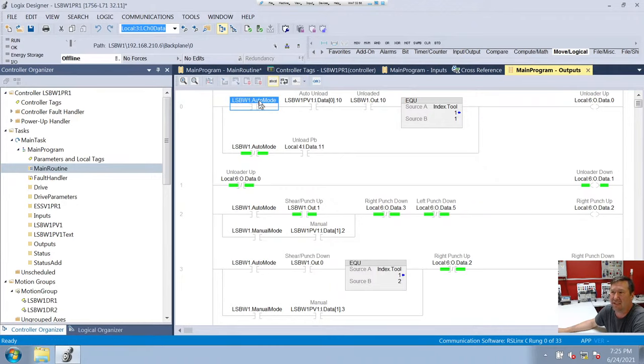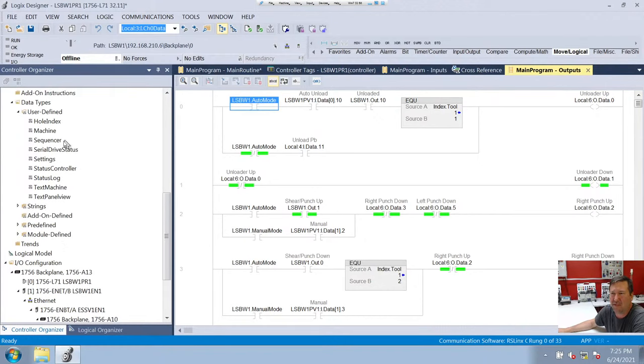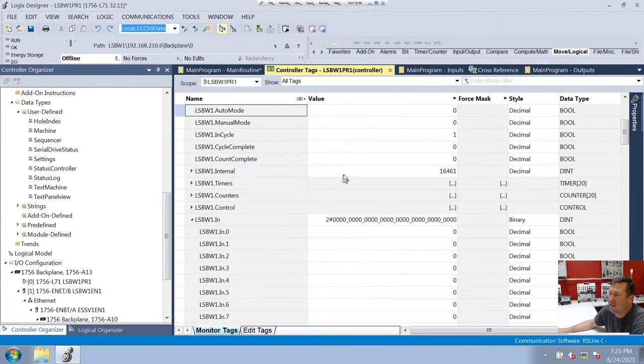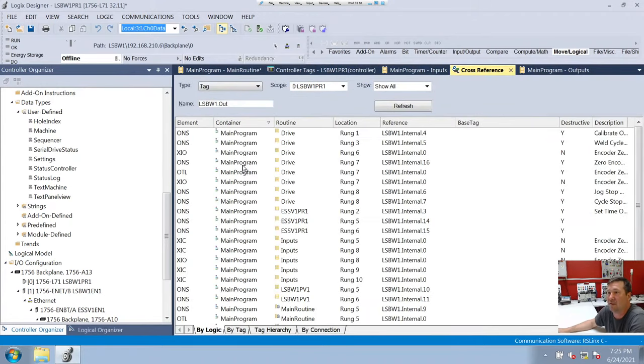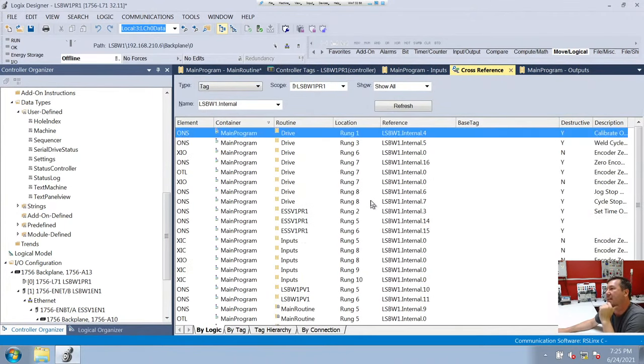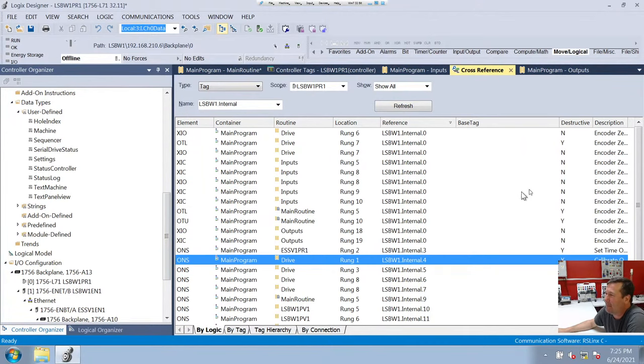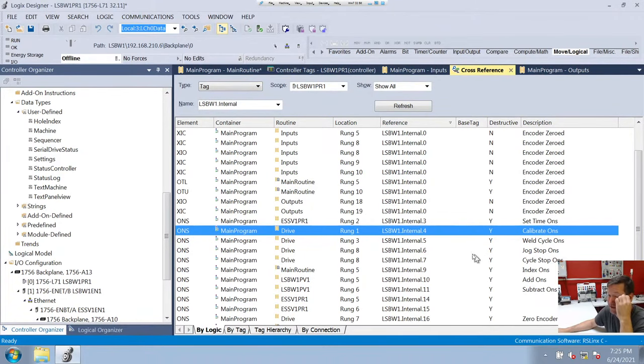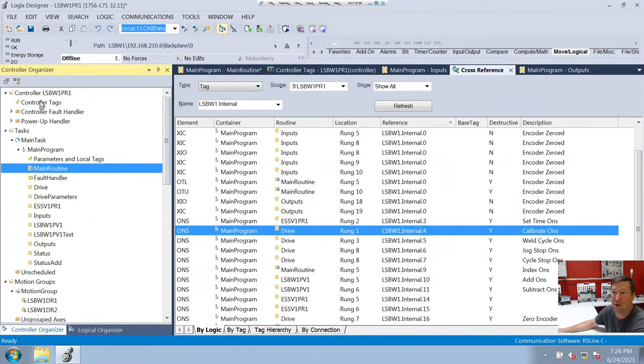I want to jump back to something about descriptions. This doesn't have a comment but I can figure it out because it's auto mode. But remember those internal ones? If we monitor the machine data type — encoder zeroed, set time, calibrate, jog stop — these are definitely used and they're not just internal things. I see this all the time in programs: a tag that is called 'bits' and every bit in that thing will be used for something in a program.